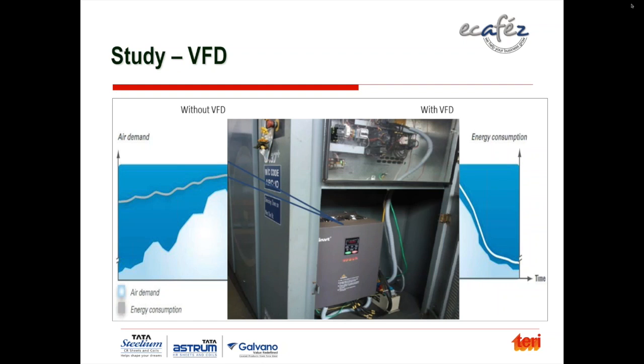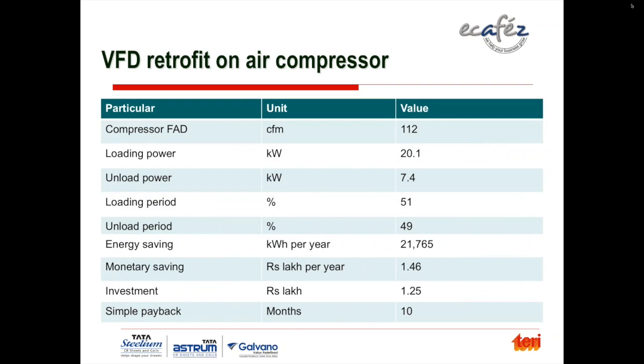This is a photograph of the VFD which was installed in the compressor air panel after the suggestion. This was the result. The compressor capacity was 112 CFM, loaded power consumption was 20 kilowatts, and unloaded power consumption was 7.4 kilowatts. This unloaded power consumption is essentially eliminated through installation of the VFD. The compressor was loaded 51% of the time and unloaded 49%.